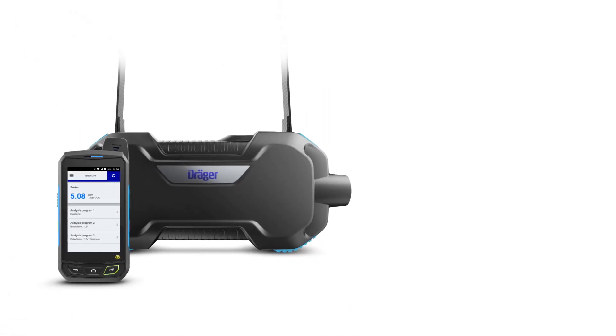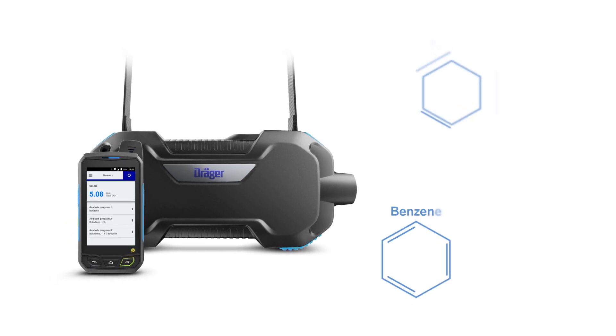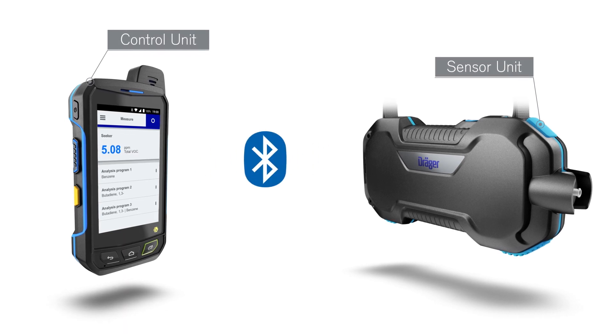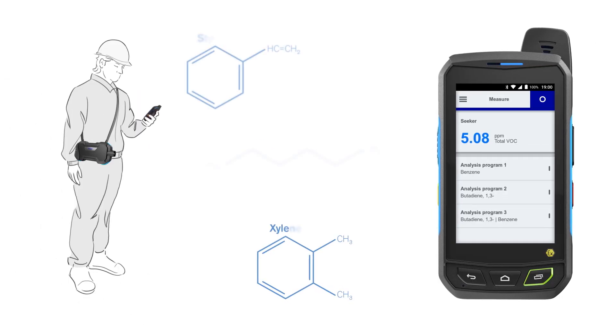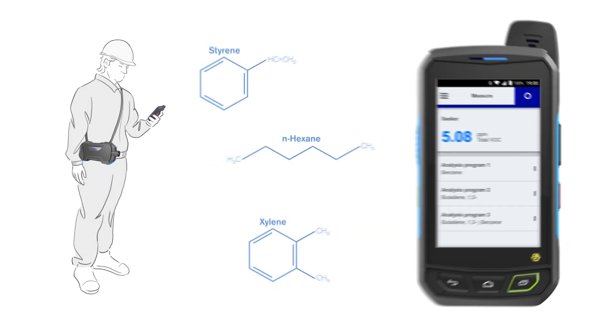The Draeger X-pid 9000/9500 is a portable gas measurement device for tracing benzene and other carcinogenic substances. The sensor unit and the control unit are connected via Bluetooth and are explosion proof. Within seconds, you can see whether a hazard exists, so you can take the necessary actions. This makes it easier than ever to monitor threshold values and check confined spaces before entering.